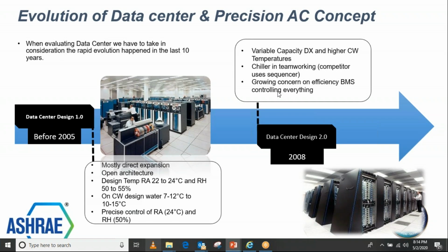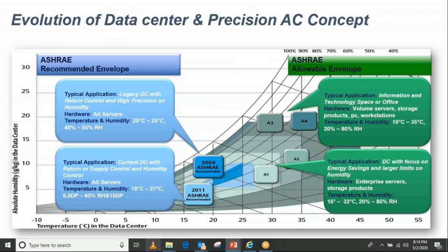The control on the BMS side also became a concern, that the cooling units should be controlled, monitored, and maintained periodically to ensure that the uptime is really high. The industry started understanding the cost of downtime, so they started focusing more and more on reliability, uptime, efficiency, and all these points of the design.